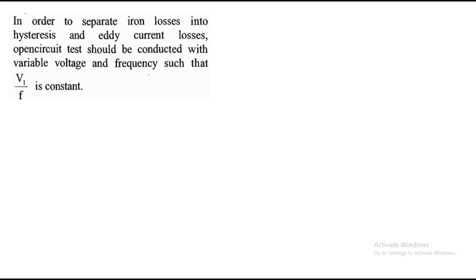In order to separate iron losses into hysteresis and eddy current losses, this open circuit test is conducted with variable voltage and frequency, such that V by F should be constant.